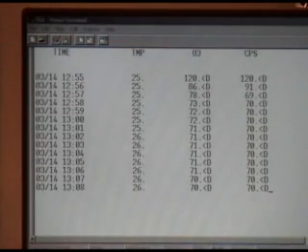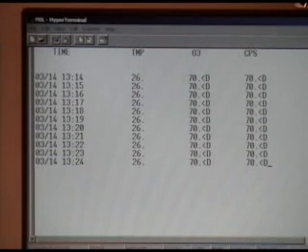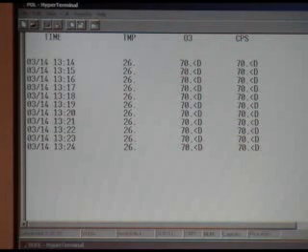As you see, we're running our last point, and slowly but surely it's drifted on down to 70, and we're probably going to let it run another 10 minutes, and we'll start taking our final readings. And you see here we got our 5 consecutive readings, and we have recorded them into the logbook. So they're looking good. So we're going to stop this event, and also stop our data collection for the thumb drive as well, per our site visit. So escape.